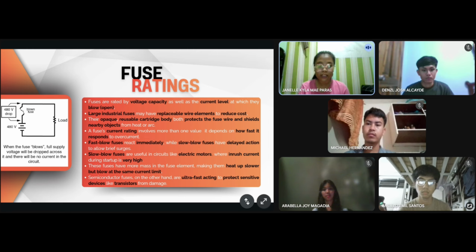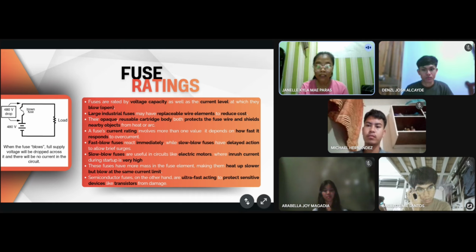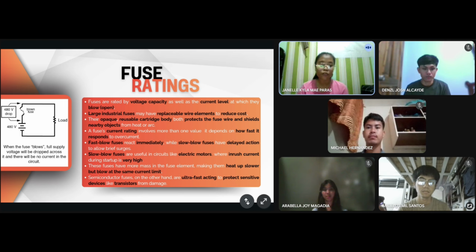Fast blow fuses react immediately to protect against sudden surges, while slow blow fuses have delayed action, allowing brief current spikes, ideal for devices like electric motors that draw high startup current. Slow blow fuses contain more mass, causing them to heat up slower but still blow at the same current limit. Meanwhile, semiconductor fuses are ultra-fast acting and are used to protect sensitive components such as transistors from damage.